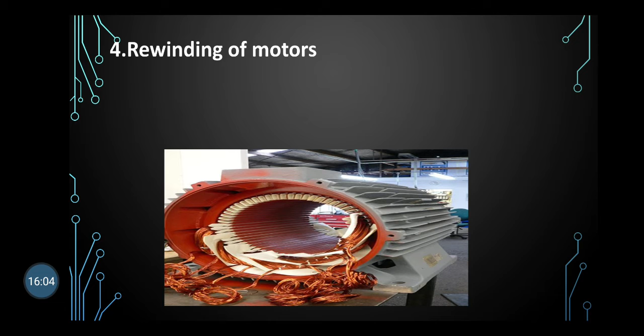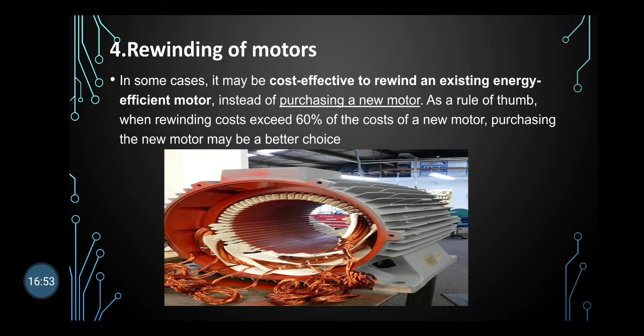In some cases, it may be cost effective to rewind the existing energy efficient motor instead of purchasing a new motor. As a rule of thumb, when the rewinding cost exceeds 60% of the cost of a new motor, purchasing a new motor may be the better choice. Because if the winding of the energy efficient motor gets burned, and the cost of rewinding exceeds 60% of the new motor, at that time it will be better to purchase the new motor.